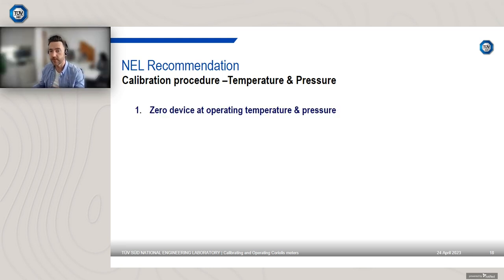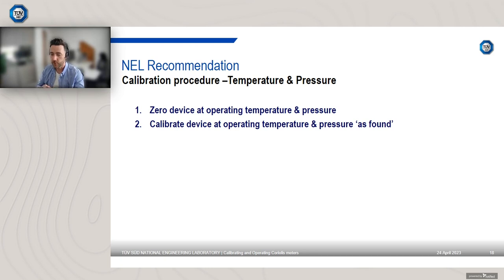What do we reach on pressure? And not too much with respect to temperature. That's because we find that the temperature effect is an order of magnitude less than the pressure effect. Now, if you think back to why that would be, Coriolis meters have an RTD on board, so they measure temperature and they also have compensation factors that automatically correct for it. So all Coriolis meters out of the box are automatically correcting for temperature. The same isn't true for pressure.